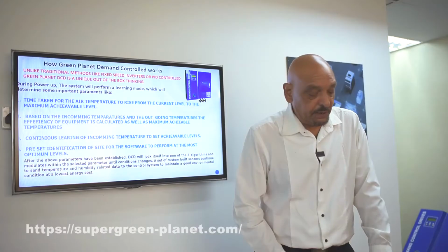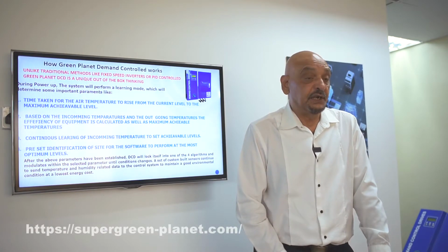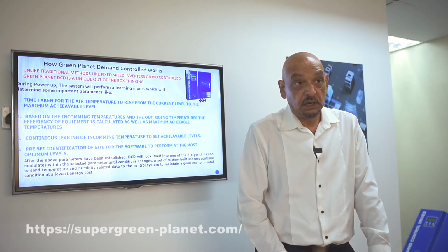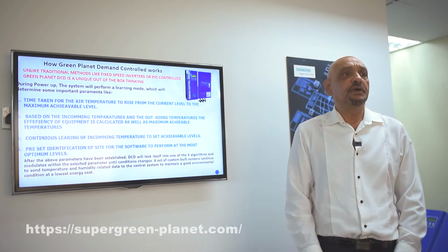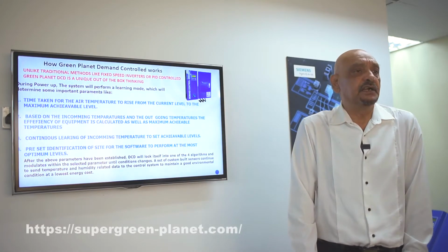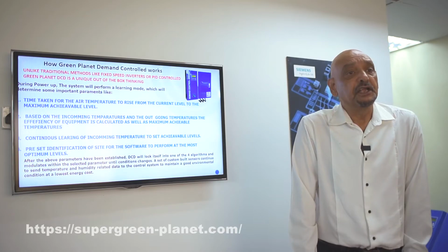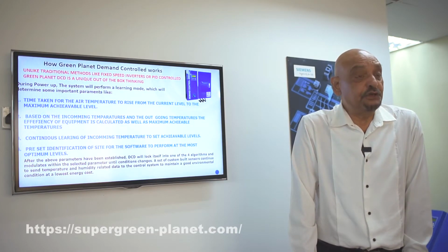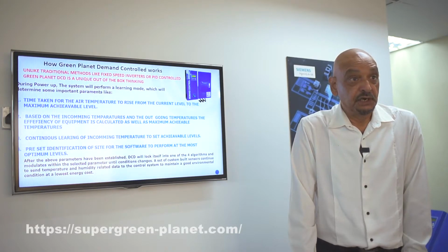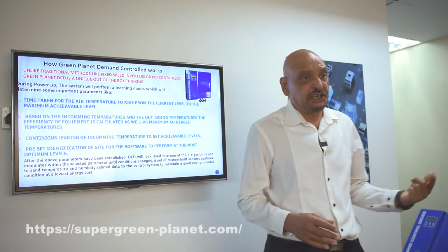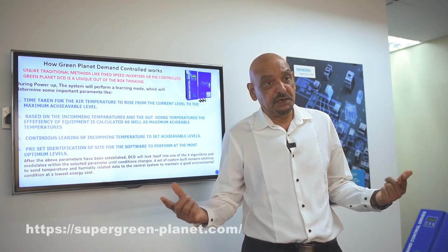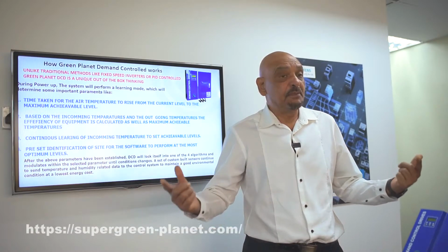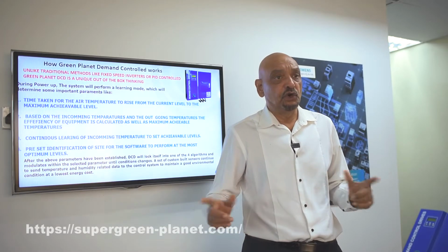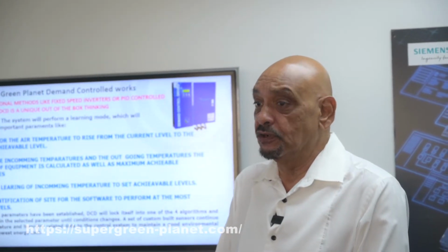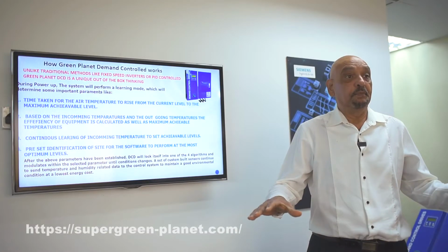Now, we all know that you may have a temperature sensor in your AHU room. You can set it to whatever lowest possible temperature you might want to. But the fact is that the AHU can only achieve what it can achieve. The system will also keep a record of, for example, the efficiency level of your current air handling unit. If you have a 18.5 kilowatt unit in one location and a 18.5 kilowatt unit in a second location, same brand, same model, it is not necessarily the case that the efficiency is going to be the same, because there are a lot of other environmental conditions within your environment that play a very important part.